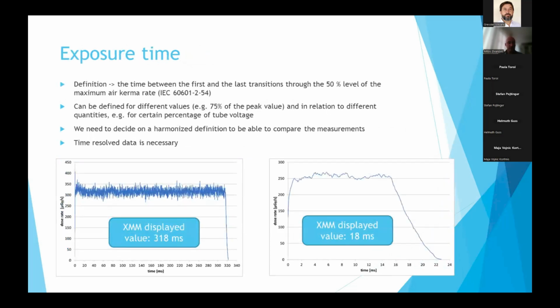And then the next quantity is exposure time. So here, again, we do not have a standard for non-invasive measurement of exposure time. And there is no central standard where you would find a harmonized definition for this quantity. So you have to look at different standards that tell you how to do quality control for different diagnostic machines. And for example, if you look at IEC 60601-2-54, there you can find a definition that exposure time is the time between the first and last transition for the 50% level of the maximum air kerma rate.